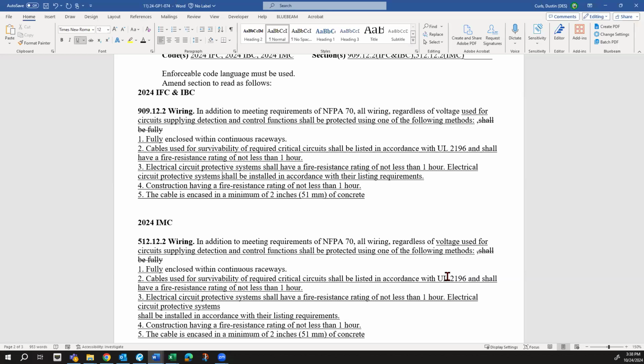For the pressurization, they're looking for the 2-hour protection, which is usually run inside of a continuous raceway, up inside of a shaft, inside the 2-hour envelope to get to the fans. If it's an elevator pressurization, it's got to come up a shaft somewhere that they dedicate for it. But the rest of the fire alarm devices are not part of that pressurization system. If it's a standalone pressurization system, anything that would be required because of the pressurization system would be in continuous raceway or survivability. But 1-hour protection is running through a sprinkled building, essentially. If you're running through a corridor in a sprinkled building with a fire alarm detector, that meets the requirement. It's not directly required for the smoke pressurization system. It's required for the fire alarm system, and vice versa.